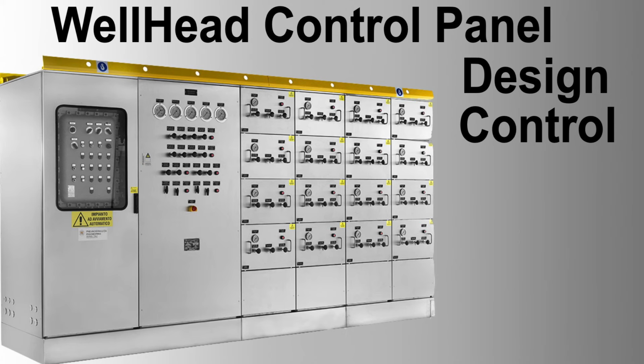Operation: 1. Normal operation. The WHCP maintains hydraulic pressure to keep the SSV open. 2. Shutdown. In case of an ESD activation or high-low pressure conditions, the PLC RTU vents the hydraulic pressure, causing the SSV to close. Control loop. Closed loop. The pressure transducer provides feedback to the PLC RTU, which adjusts the hydraulic pressure to maintain the SSV in the desired state. Feedback: real-time pressure data from the transducer. Control signal: hydraulic pressure regulated by the PLC RTU.